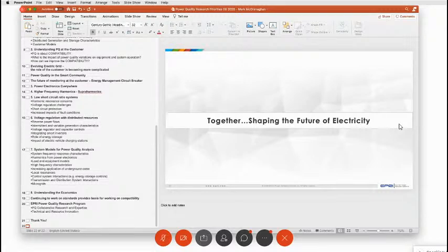But you also need to consider in your harmonic analysis the inrush to transformers, in particular because you might design filters to solve harmonic problems with your traditional loads like adjustable speed drives, and those filters might cause a resonance at the fourth harmonic. And then you think, okay, we don't have any fourth harmonic. But when you energize transformers, that inrush current does have fourth harmonic, so you can excite a resonance that you've created by doing your filtering for other loads. So for both of those reasons, it's important to consider inrush characteristics as a power quality concern.